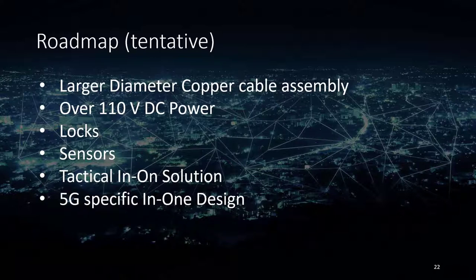In the roadmap — this is not committed yet, but it is a serious roadmap — and if you have any questions in the Q&A sessions, you can put them directly to Carl Uwe. We have a larger diameter copper in the cable assembly, which means two things: we can have more DC voltage and longer distances, which is extremely interesting. The other development is up to 400 volt DC, which is over 110 volt DC. One thing to note: the European safety standard maximum for DC voltage is 110 volt DC. The American standard is, I'm not sure if it's 50 or 55 volts DC. So there is a limitation with any similar or competing product to the N1 if it's American, because it's much less voltage, meaning much less devices and much shorter distances.